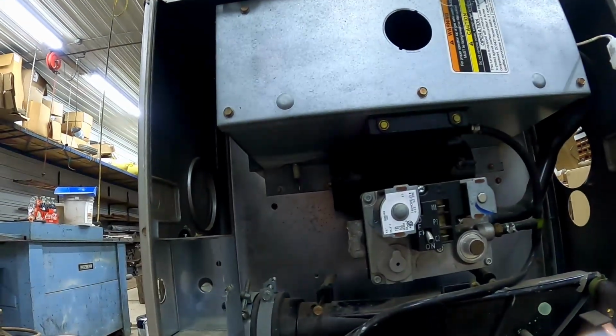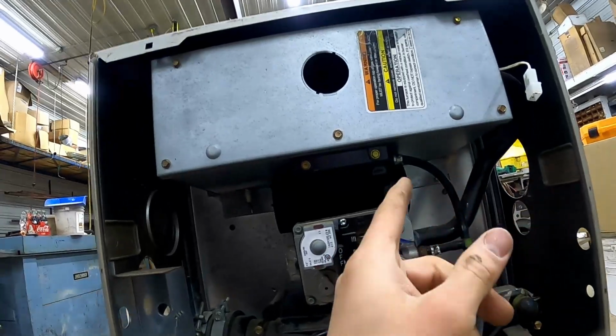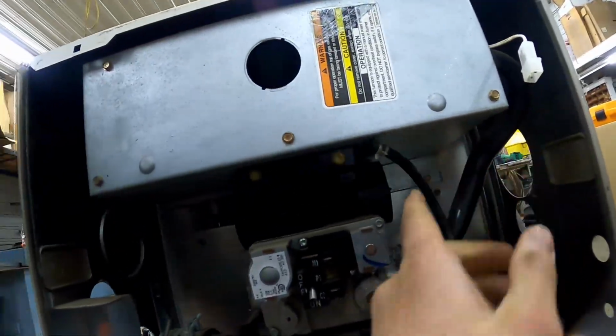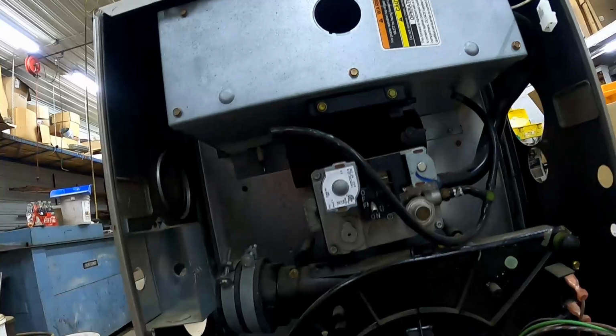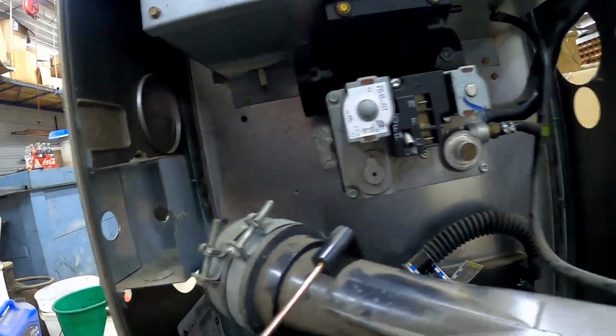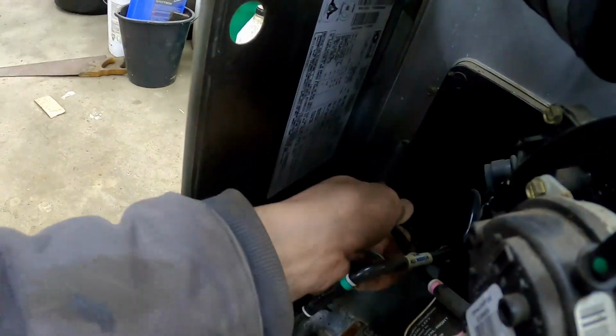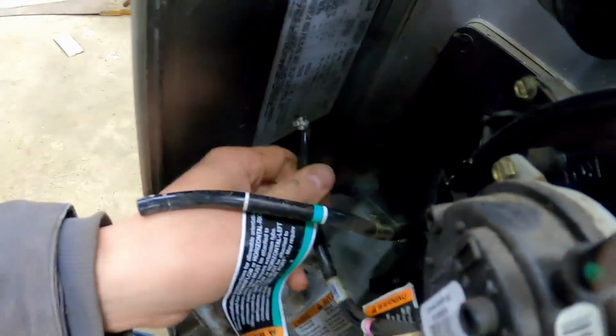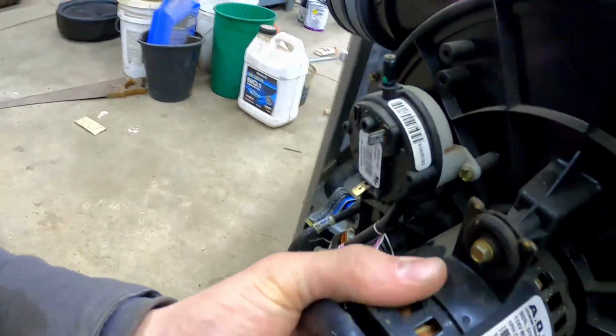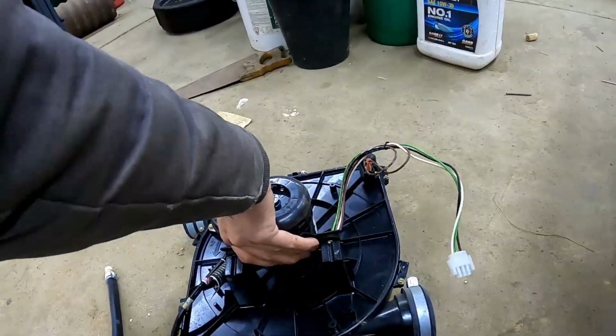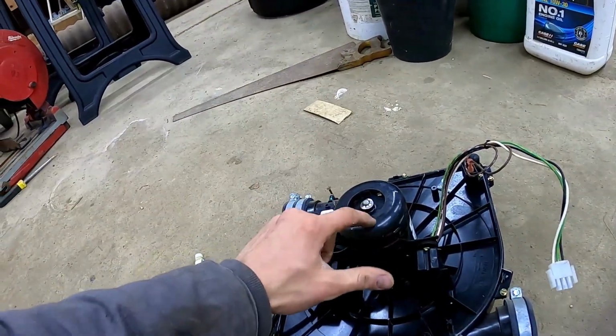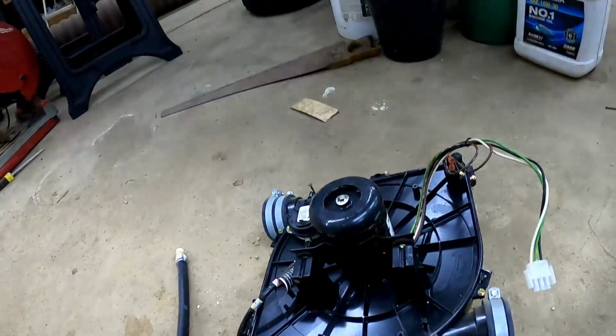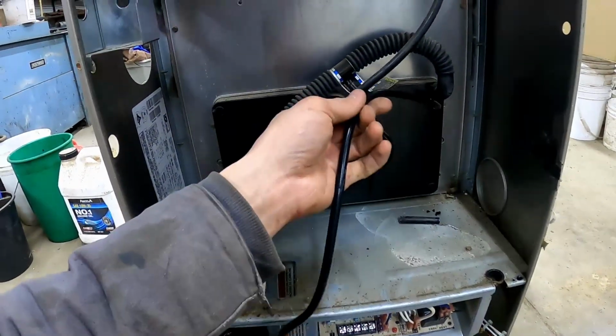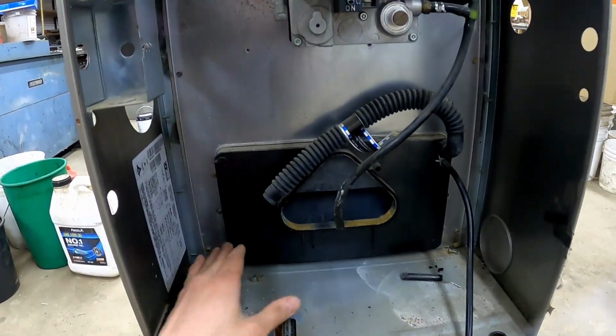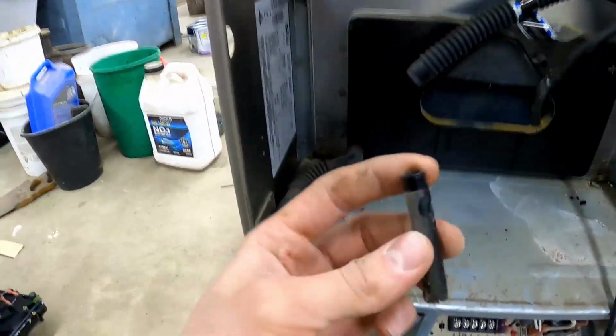Then we're just going to leave the pressure tube that goes up to the gas valve and burner manifold attached to the gas valve like that. We can lift this out. And our other pressure tube goes down to here. But we're just going to pull it off that way so it stays with our combustion blower. It's very important to be careful that it doesn't tip against this, because I've had it tip before back onto this and break that off. And then these tubes I try to leave on there until we have our new heat exchanger in place so that we remember exactly where they go. These are important. That's one of the feet for the combustion blower.